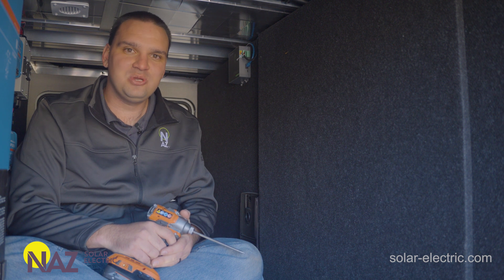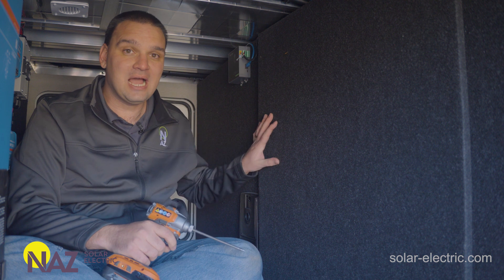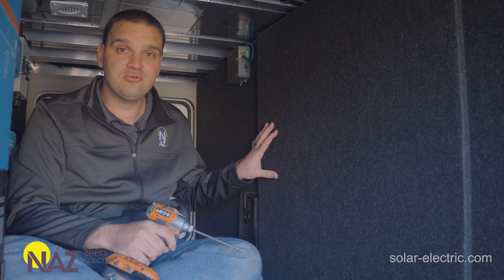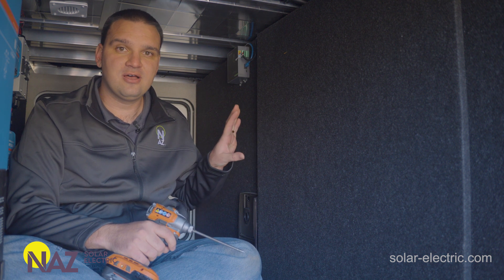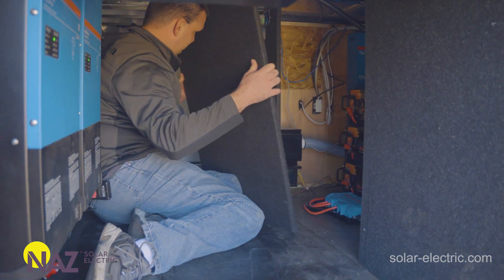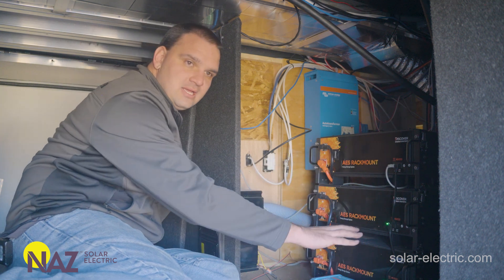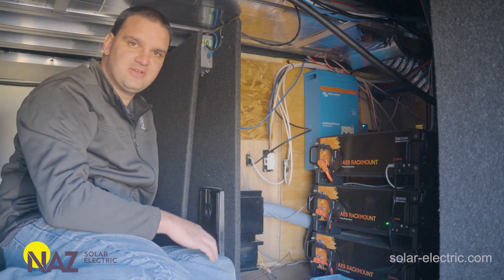Now let's look at an actual system with these AES rack mount batteries installed. In this system, we have a unique, custom-engineered battery solution. Behind this wall, we have Discover AES rack mounts — three batteries totaling about 15 kilowatt hours of battery capacity in closed-loop communication with Victron. We have three batteries all paralleling with individual cables into this Lynx Power In that then feeds the Victron system.